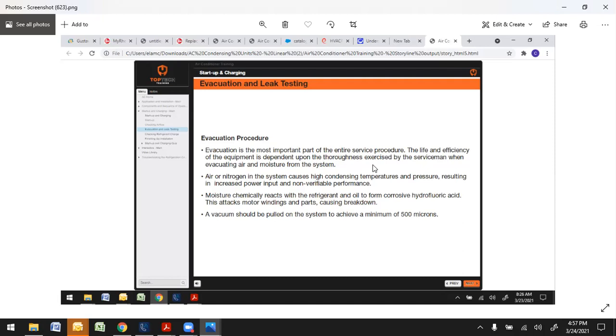Air or nitrogen in the system will cause high condensing temperatures or pressures, which will result in increased power input and non-verifiable performance. You'll be able to tell because in some cases you'll see your head pressure bouncing up and down. I've had old manual gauges that would actually physically vibrate my hands. If you come across head pressure just bouncing up and down, you've got non-condensables in there. Somebody didn't take the right procedures when setting that up.